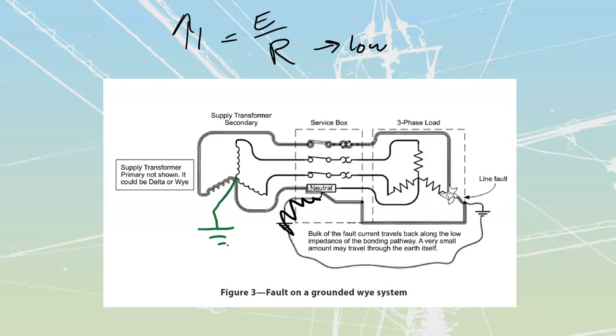If I take a look at the path over here, if I ground it at the actual transformer, you'll see that you still have a complete path for current flow going all the way back, because my bond, I should actually just draw that in first, my actual bond itself would have to be attached from here out to this ground as well. That's just the rules of bonding, that the bond has to be attached at the actual grounded neutral. So what I would see over here is an attachment that goes all the way back to there.